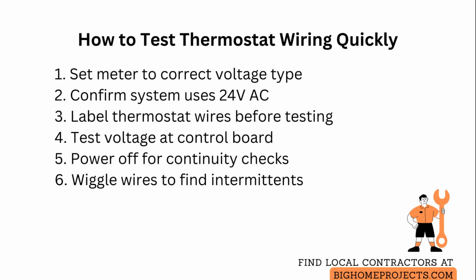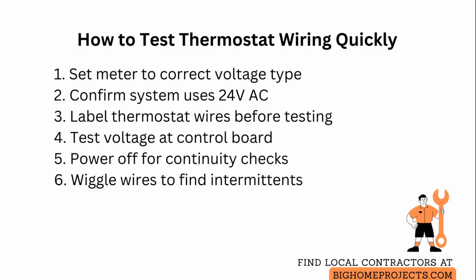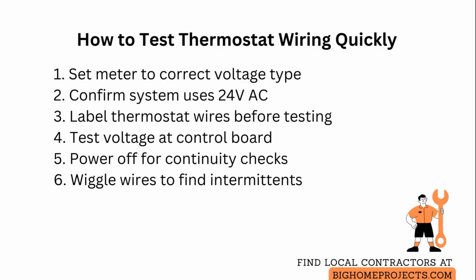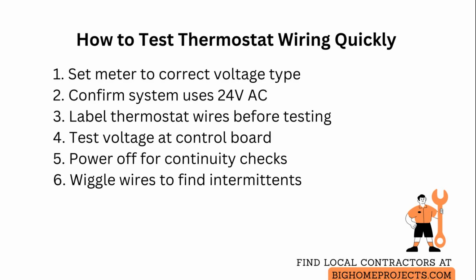To verify a call for heat or cool, place the multimeter probes between the common terminal and the terminal for the call function. If the thermostat is calling, you should see nominal control voltage. If no voltage appears but the thermostat display is powered, suspect a broken wire or a failed transformer.